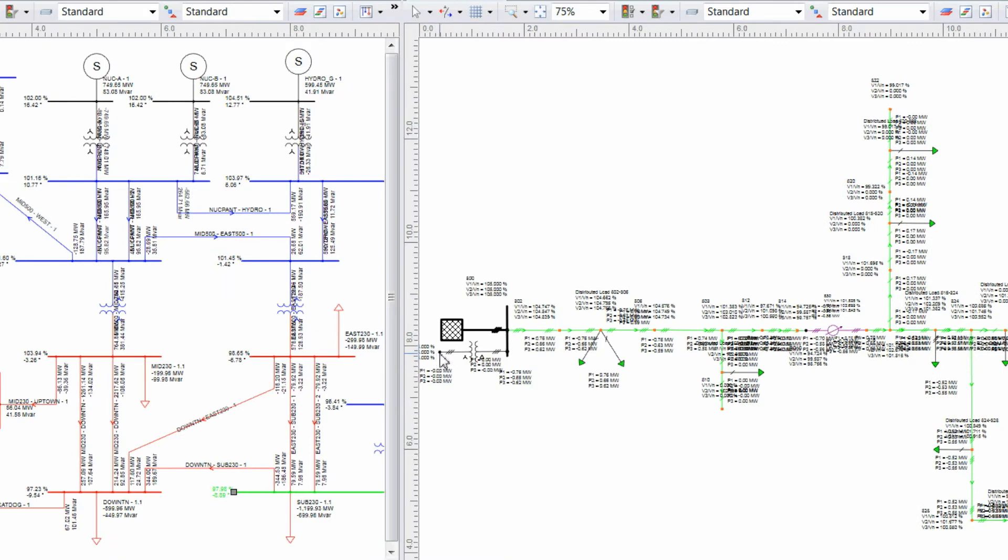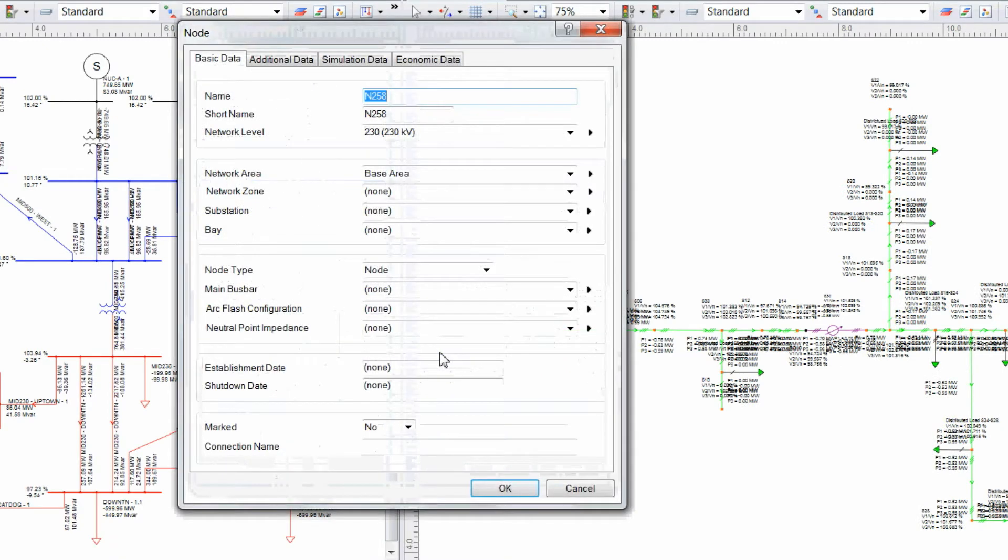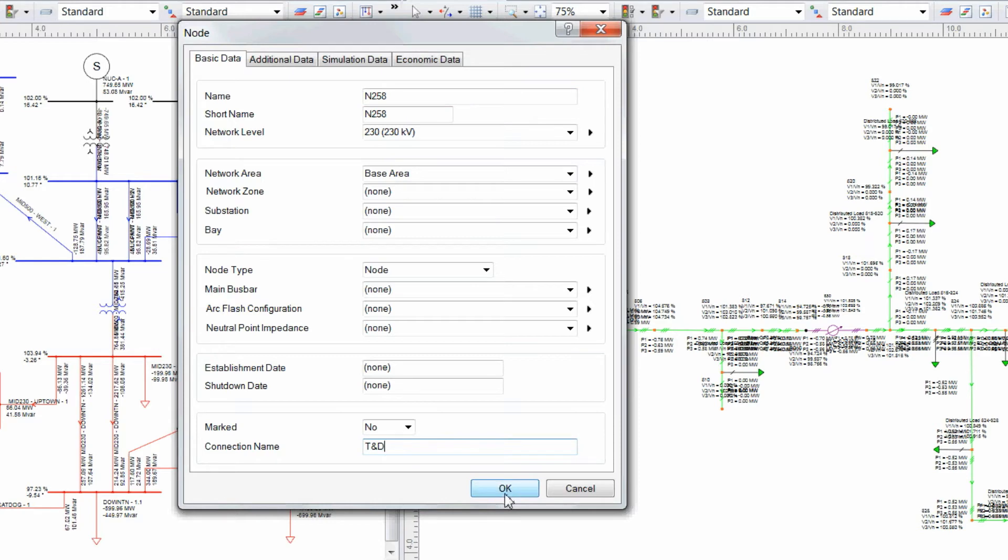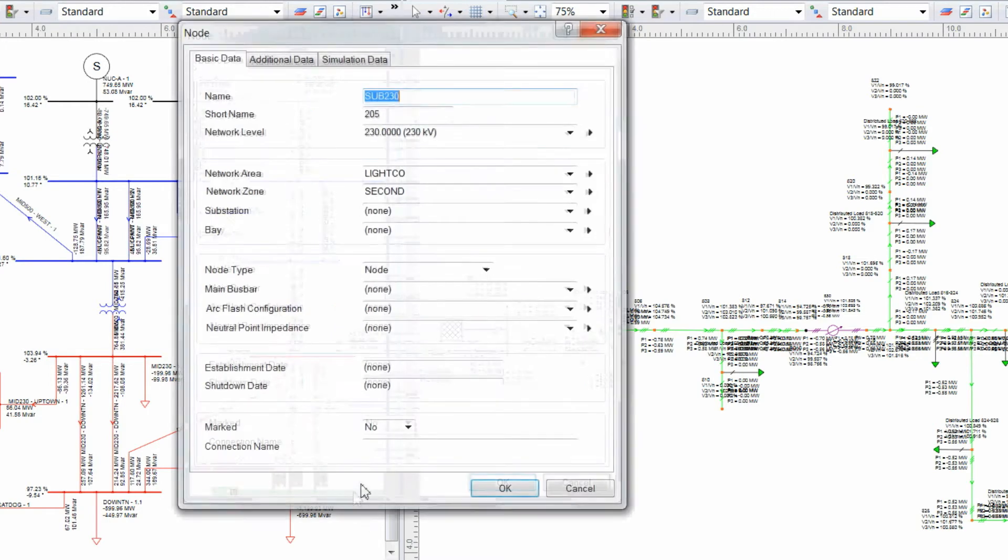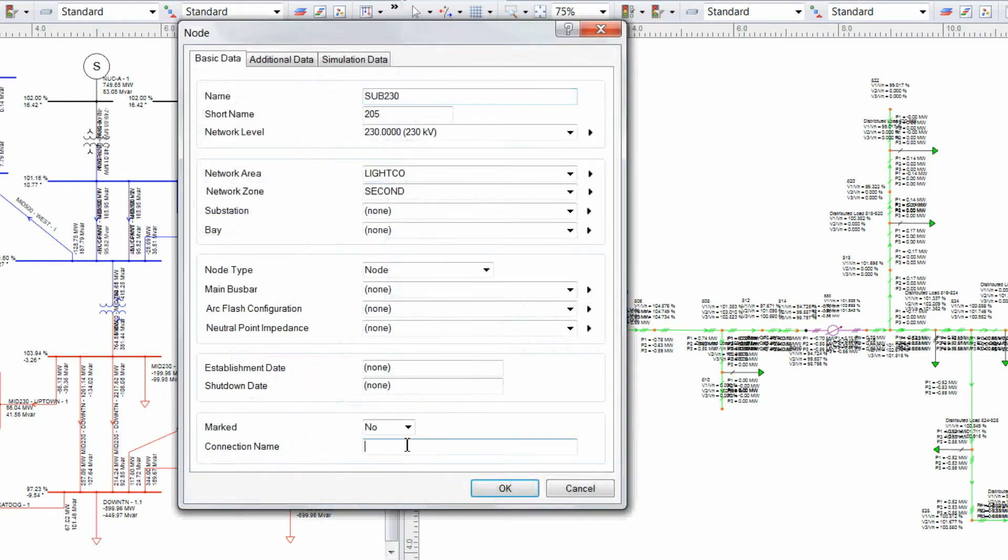Next, change the node on the high side of the transformer in the distribution network, and create a connection name. Repeat the same process on the transmission side. Pick a 230 kV bus, and connect them by using the same connection name.